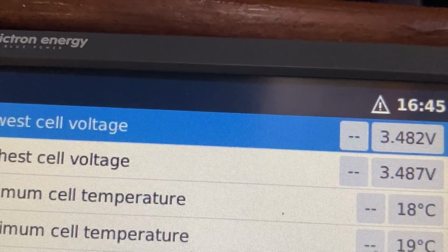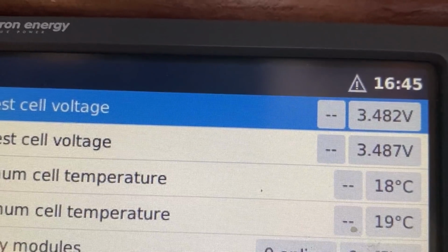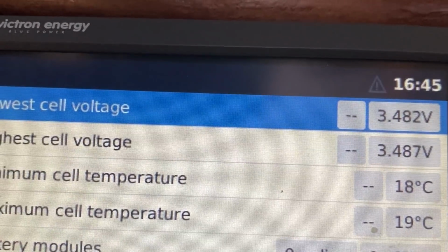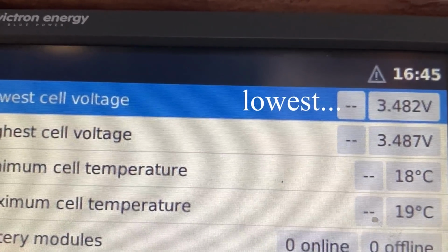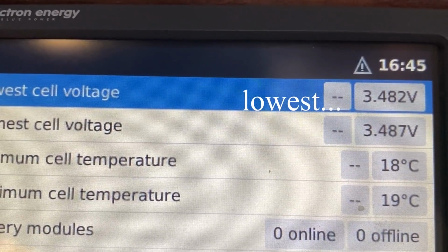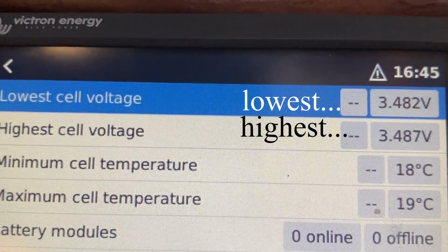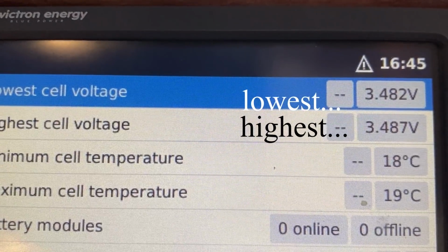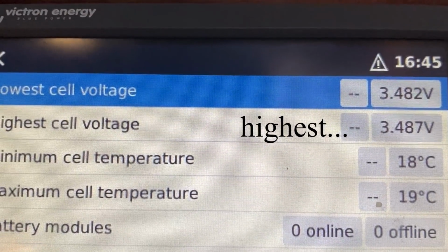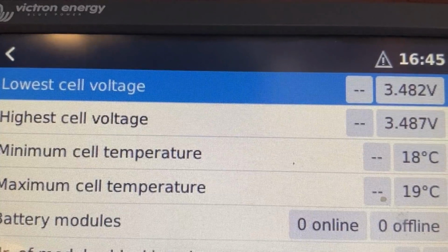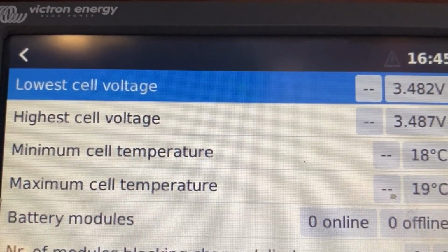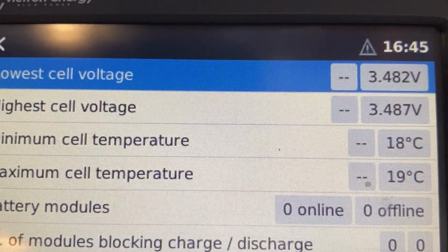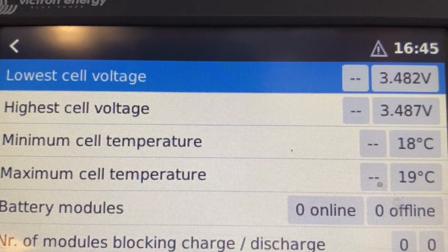Lowest cell voltage on the top line, highest cell voltage. So the lowest cell voltage of the 8 cells in there is 3.482. The highest cell voltage of all 8 cells is 3.487. That's very, very close to each other, which means all the cells are closely balanced, which is really important.